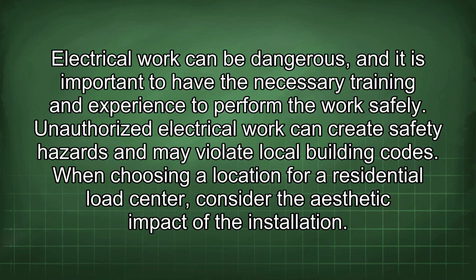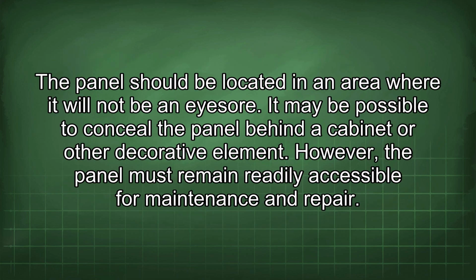When choosing a location for a residential load center, consider the aesthetic impact of the installation. The panel should be located in an area where it will not be an eyesore. It may be possible to conceal the panel behind a cabinet or other decorative element. However, the panel must remain readily accessible for maintenance and repair.